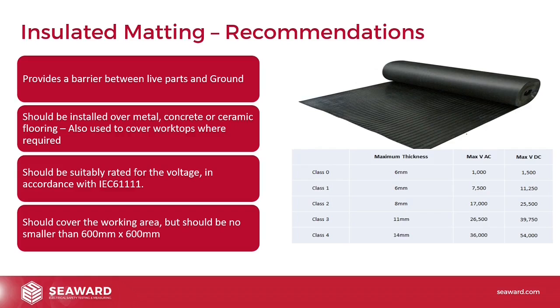And it should be suitably rated for the voltage that you're using in accordance with IEC 61111. So in terms of the kind of tester that we'll talk about today, possibly is a unit we call our HAL, and it has a max output of about 6,000 volts, and so we would need a class 1 mat for that, because even if we were testing at, say, 1,000 volts AC, we need to think in kind of worst case scenarios.